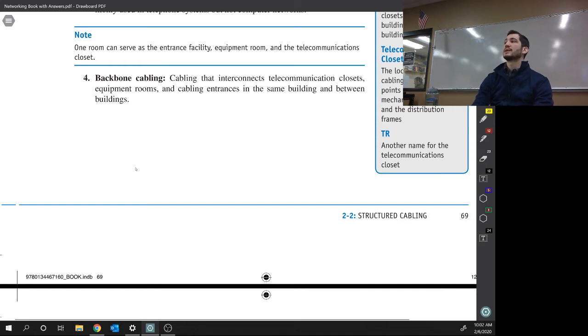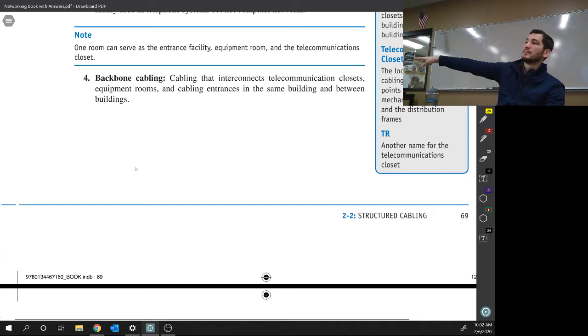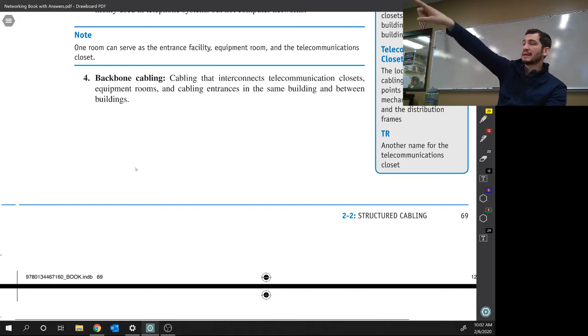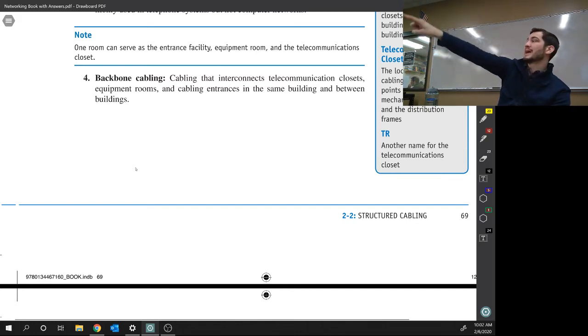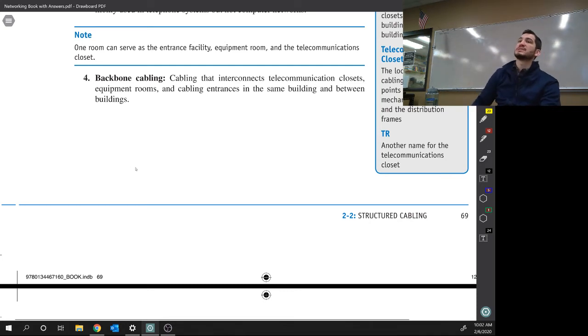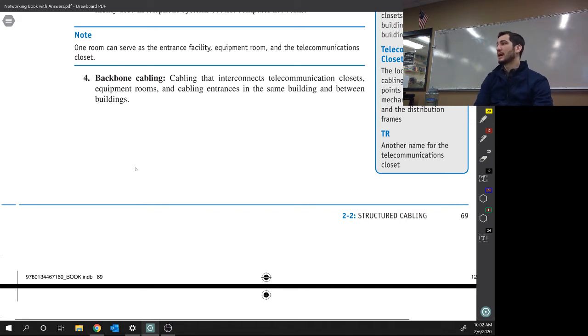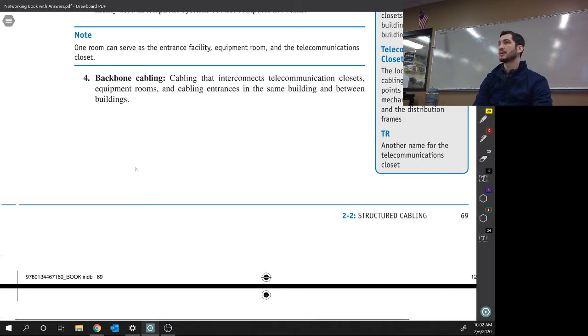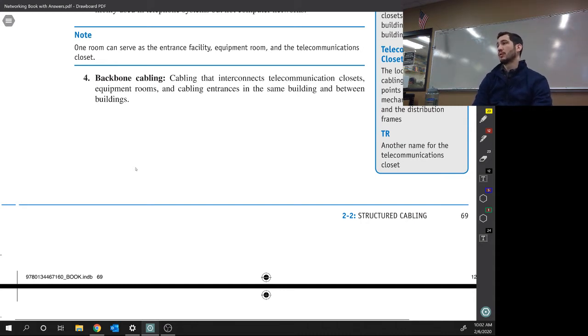So one of the things when you're pulling cable is you can't just go, okay, I want my jack right there, so I'm going to pull my cable right there. Because the chase into this room may be back in that corner. So you have to pull cable to go to the chase and back. So you always, it's always better to pull more cable than you need than to not pull enough. Because a thousand feet is about a hundred bucks, so I think that's ten cents a foot. And to pull a cable an extra thirty feet, that's an extra three dollars. It's not that big a deal.